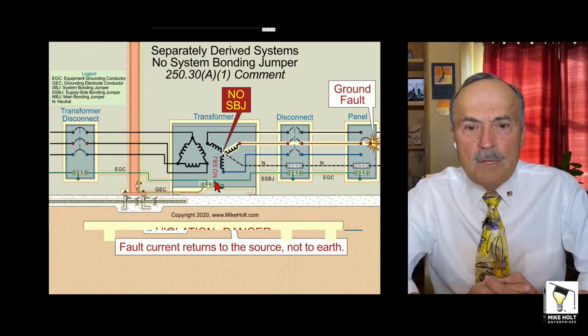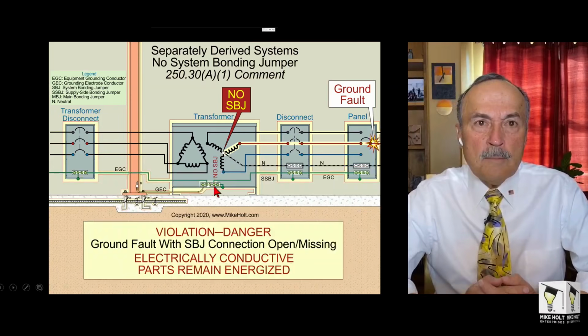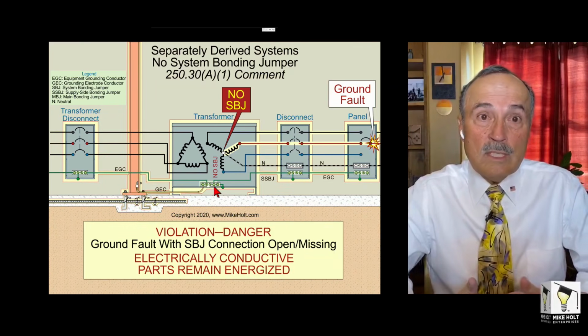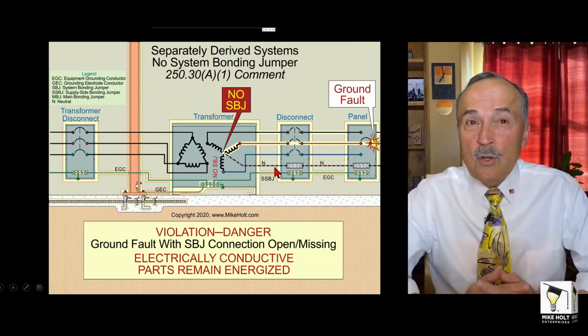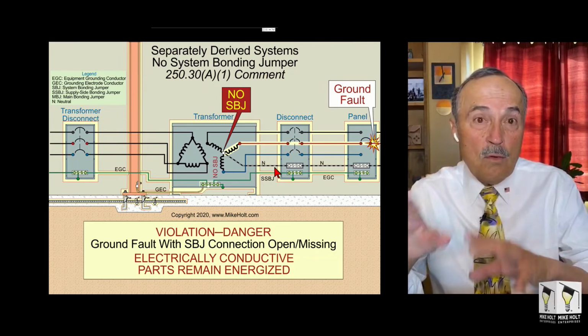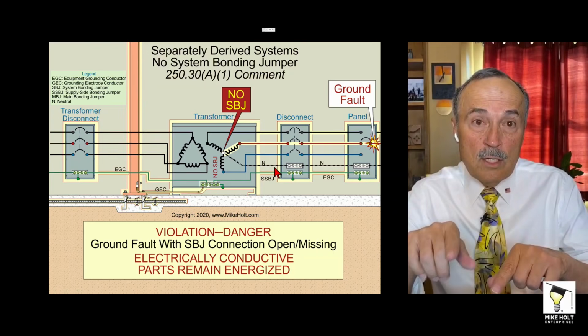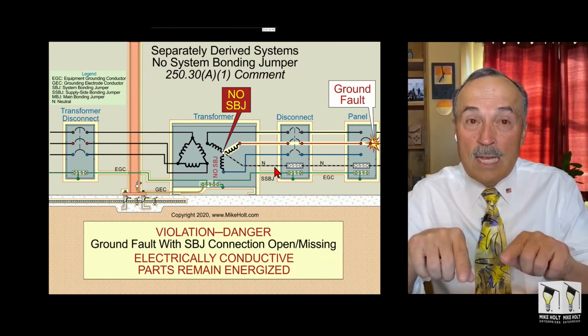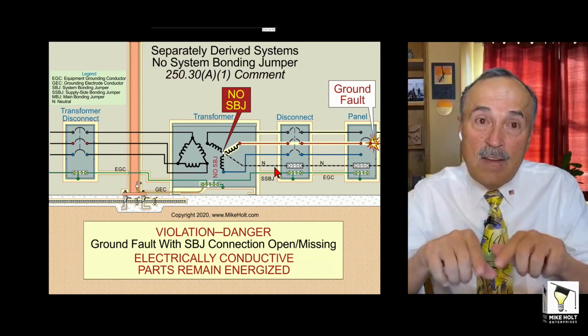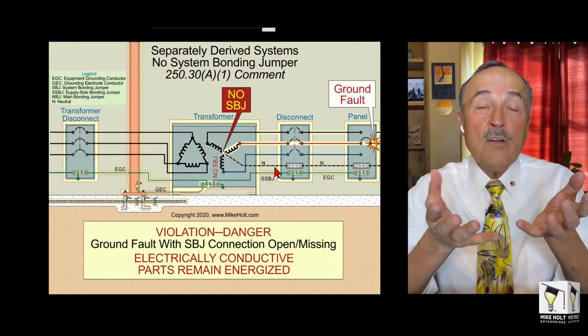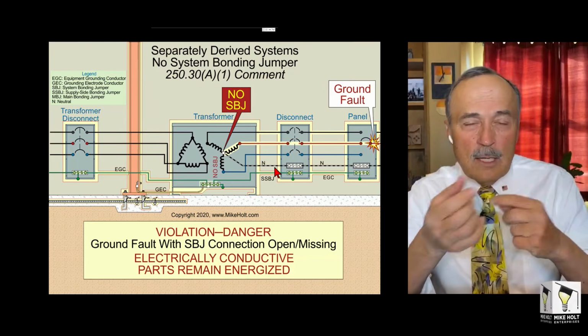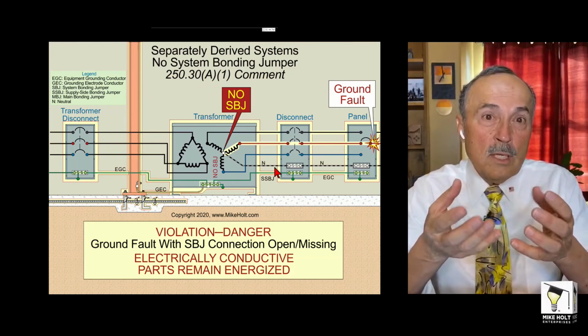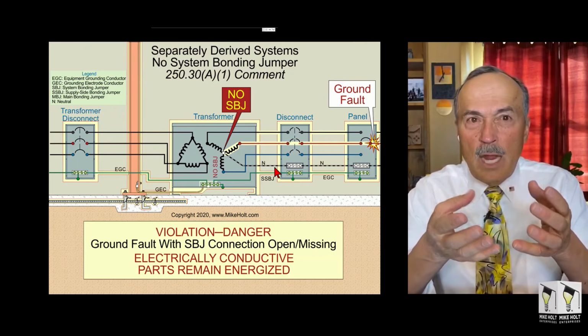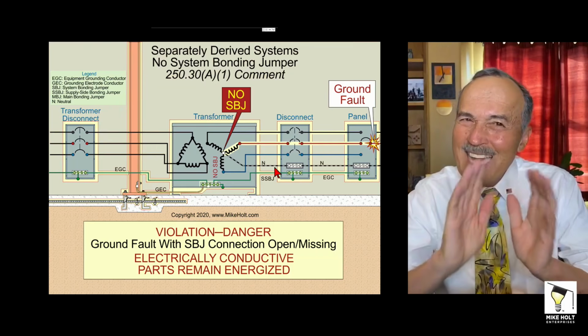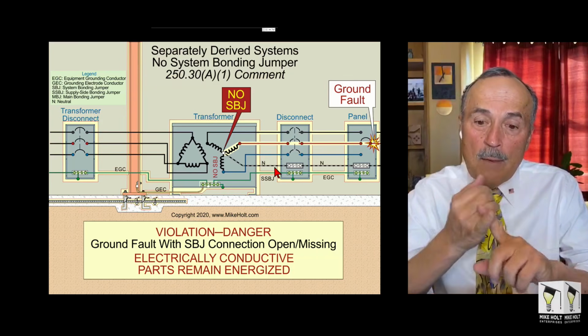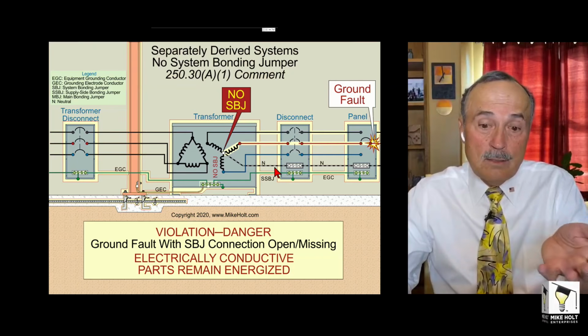All right, but what happens if a person doesn't install the system bonding jumper? Well, guess what you have? You have an ungrounded system, which was not intentional. And since you have a neutral, it's 250.20 that talks about what systems are required to be grounded. If you have a neutral, and it's a 120/208 or 277/480, it requires that system to be grounded. So this is a violation of that rule. In addition, you have an ungrounded system, and we didn't get into it, but Beeman's book talks about ungrounded systems and the problems. There are like nine different scenarios where you'd have a problem with an ungrounded system. That's why it's not a favorite system. So you're going to create problems with an ungrounded system, and you can't clear a fault because there's no fault return path.